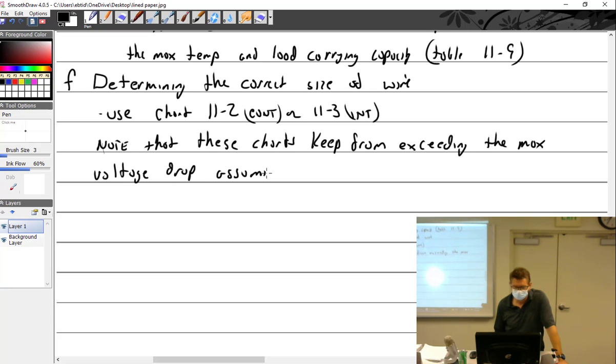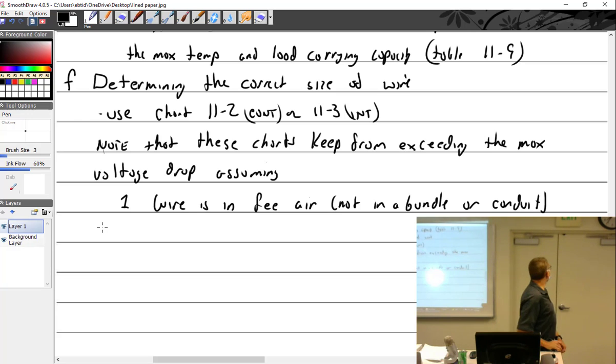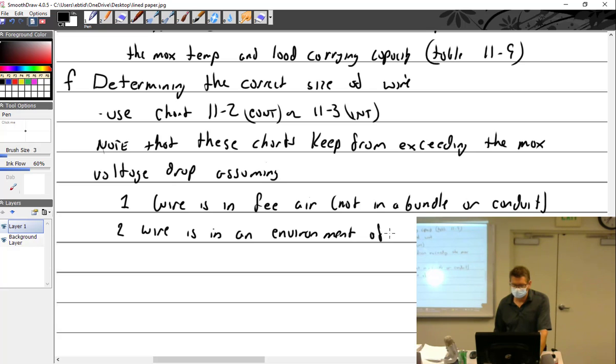So let me see, voltage drop assuming a few things. One, wire is in free air, not in a bundle or conduit. What's conduit? Conduit is metal tubing where wire runs through it - oh, right there next to you, there you go, conduit. And wire is in an environment of 20 degrees C or less, which is 68 degrees F or less.